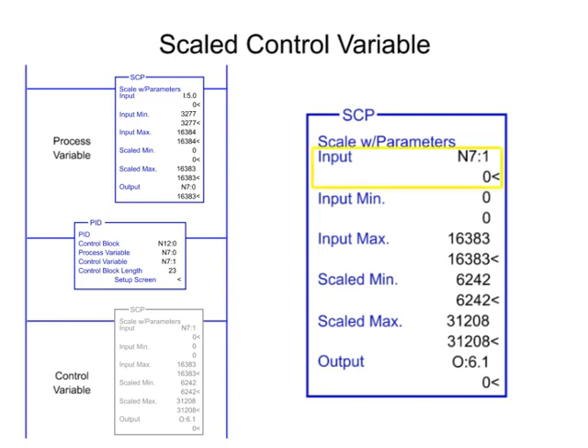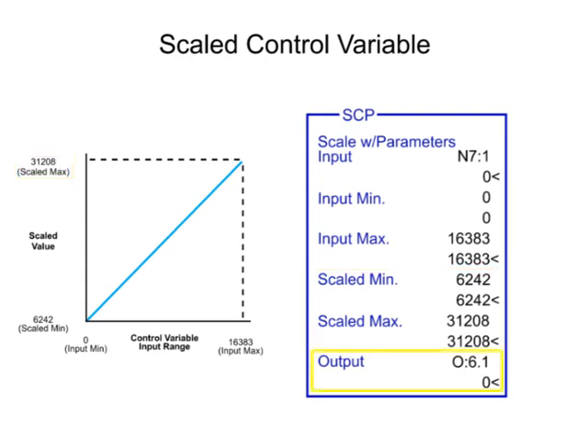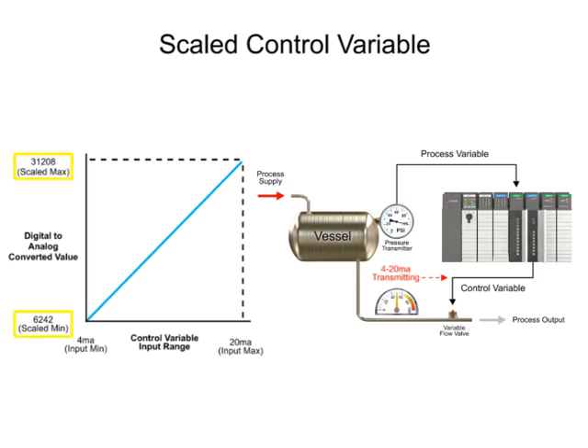The input parameter of the SCP contains the memory address of the PID output values that will be scaled. The input minimum and input maximum are programmed as the smallest and largest values of the input range. The input value is then scaled between the ranges programmed in scaled minimum and scaled maximum parameters. Scaled minimum value is programmed as 6,242, representing the low end of the analog output module range. Scaled maximum value is programmed as 31,208, representing the high end of the analog output module range. The SCP output parameter is the file address of the analog output module. The analog output module converts the digital value in the range of 6,242 to 31,208 to an analog signal of 4 to 20 milliamps.